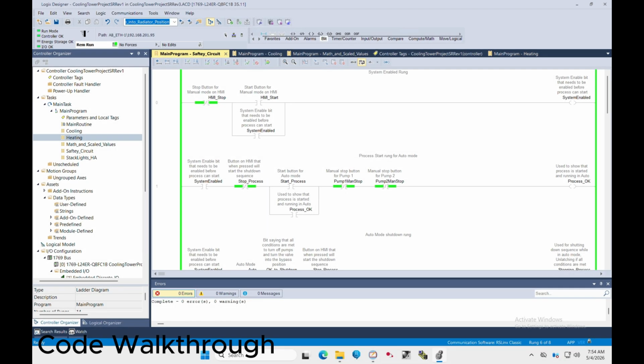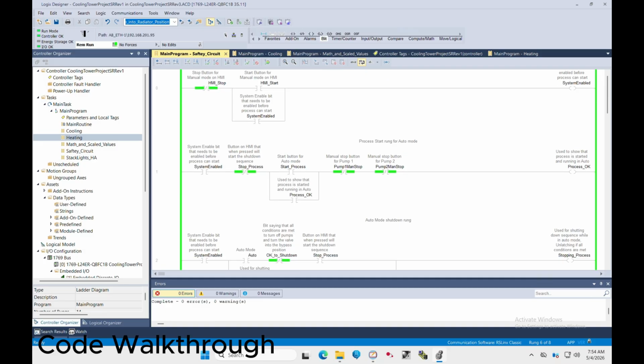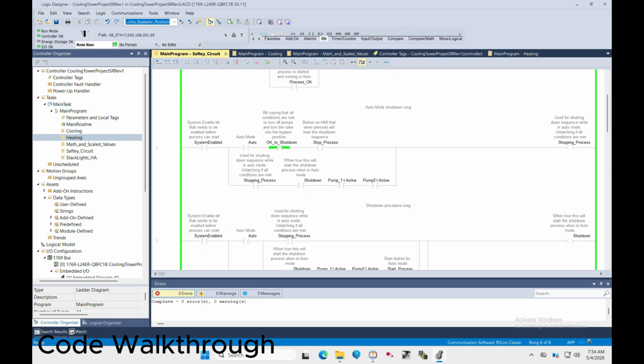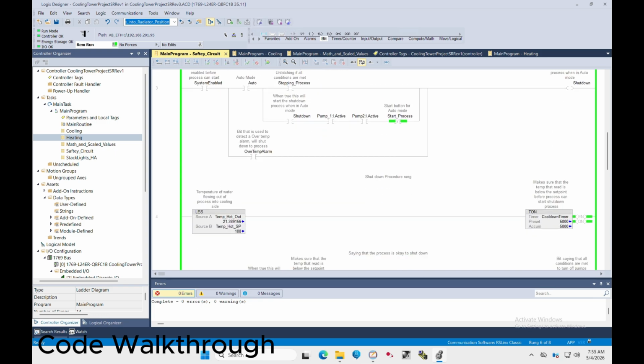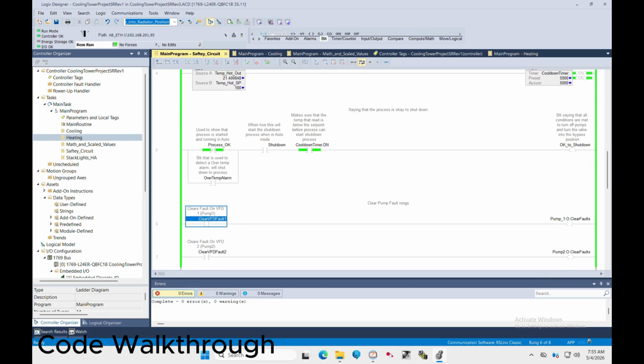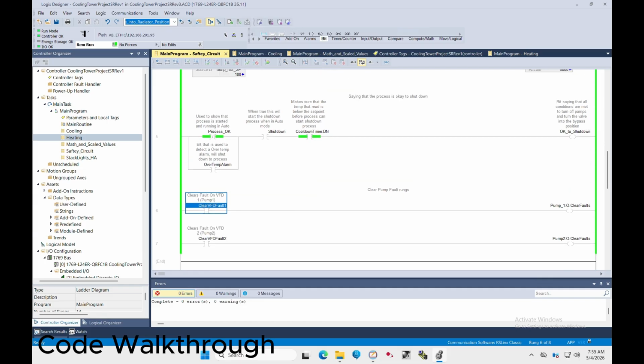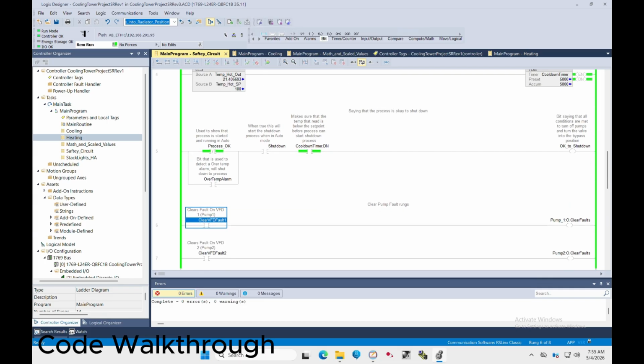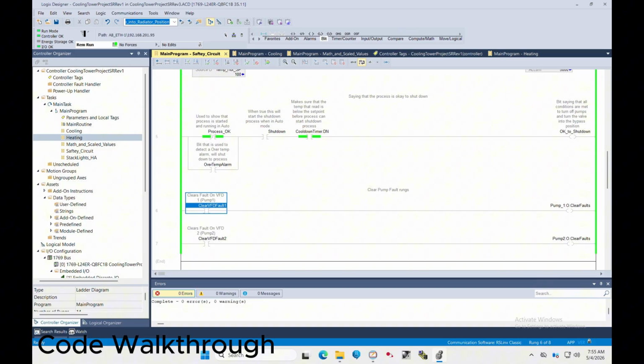And for my project code that I did, this is it right here. So I'm just going to start the safety circuit. So I got my system enabled rung, process OK, stopping process, and shutdown rung. And another rung saying when it's okay to shut down. This is my start and stop sequence pretty much right here. I also got my clear fault buttons down here too.